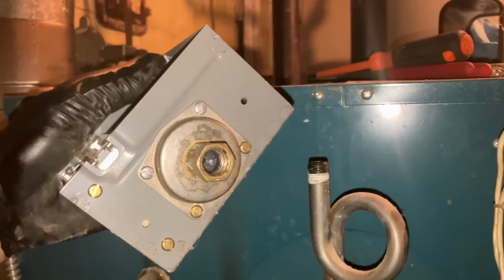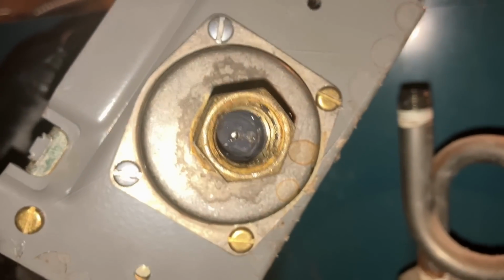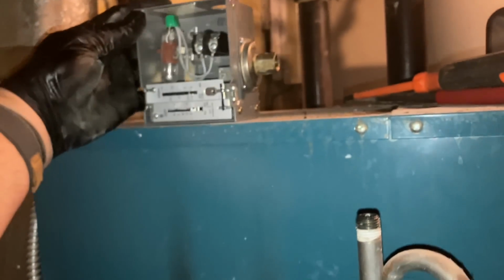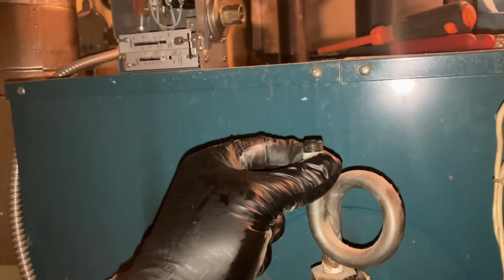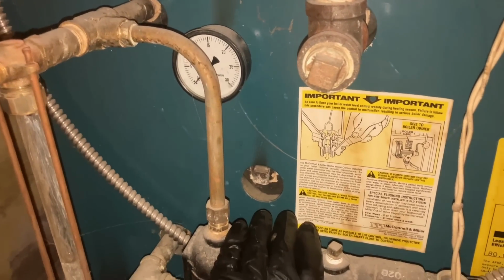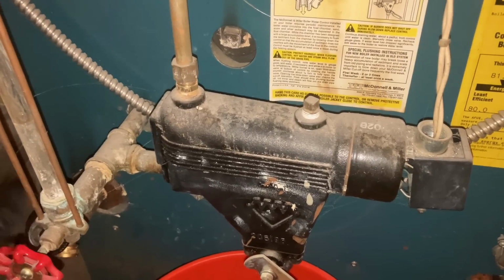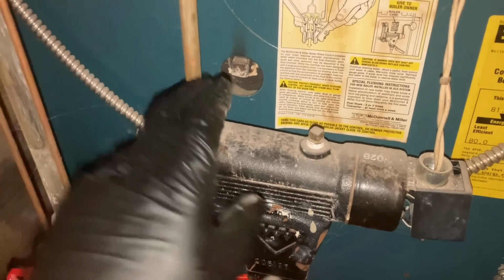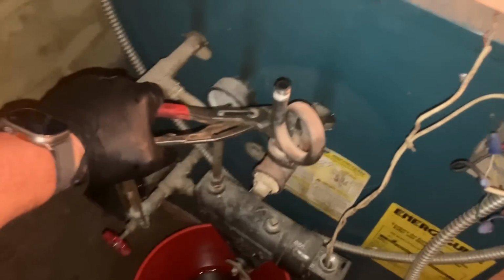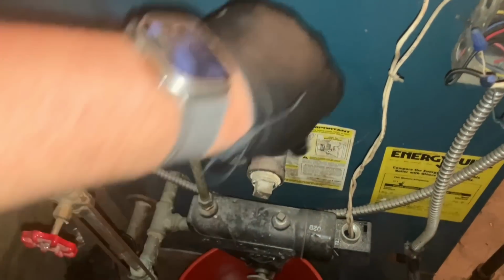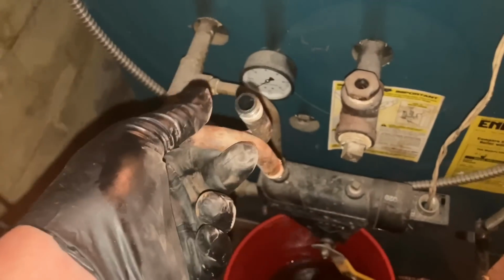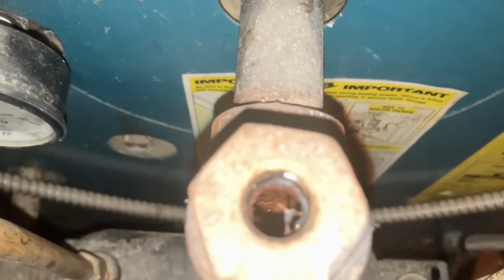Okay, and just a word of advice, besides being careful so it doesn't drop into a bucket of water: when you take off these pressuretrols, there may be water coming out of here under slight pressure. If your electronic low water cutoff is directly below it, that water is going to drip onto it, it's going to take out the low water cutoff, and you'll be putting in a new one. So be careful. Put a rag there if it's the electronic one. This one can take the abuse, obviously. Okay, now we're taking off the pigtail. We're going to see if we can blow through this bad boy. What do you think? Think we can blow through it? Let's see.